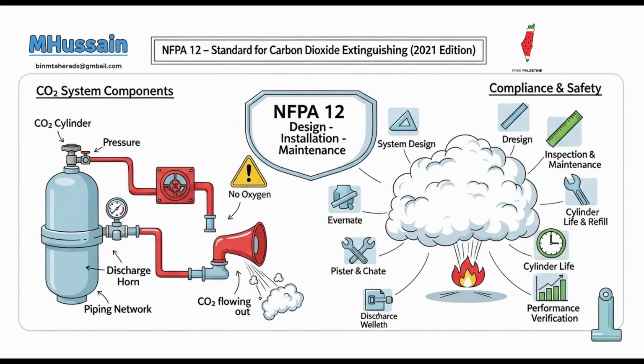Here's where it gets really interesting, and for me, perhaps the most critically important aspect of today's deep dive. Personnel safety. The absolute priority. The standard emphasizes, quite starkly, that the most significant hazard of CO2 fire suppression systems is to human life. It is. It's not the fire itself, but the agent. This is where the engineering truly has to balance powerful fire suppression with incredibly meticulous protection for people. What's fascinating here is that the inherent dangers of CO2 discharge at fire extinguishing concentrations are severe and multifaceted. The primary hazards are rapid suffocation. Suffocation, number one. Caused by the displacement of oxygen in the breathing atmosphere and significantly reduced visibility both during and immediately after the discharge. Can't see, can't breathe. Terrible combination. It makes rapid evacuation extremely difficult.